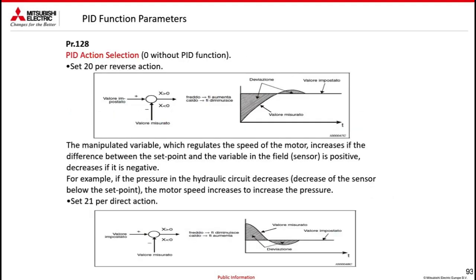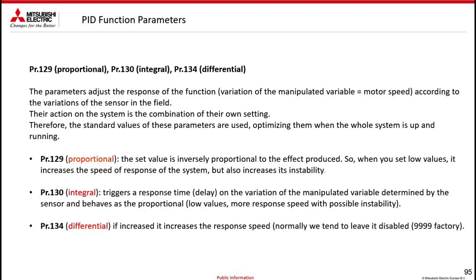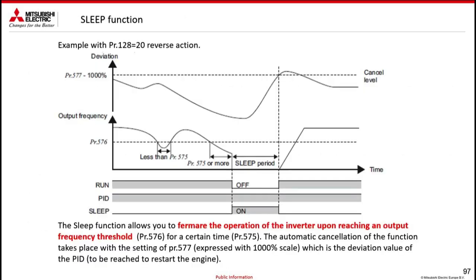The reverse function rather than direct. Set point, the possibility of modifying the gains. So proportional gain, integral gain, and differential gain. PID lower limit, PID higher limit, the possibility of managing such signal also through communication rather than enabling the sleep function. So if I am below a certain frequency value for n seconds, I fall asleep. In the true sense of the word, the motor is left to run, and when it is requested again for operation, it starts again, and so on. But I would say not to dwell too much on this part here.